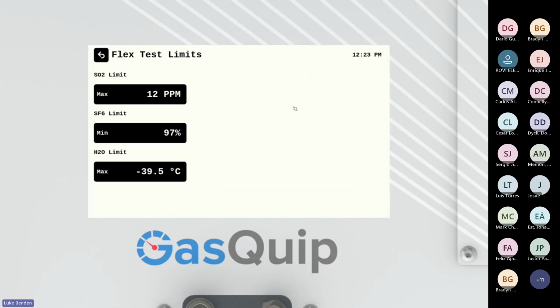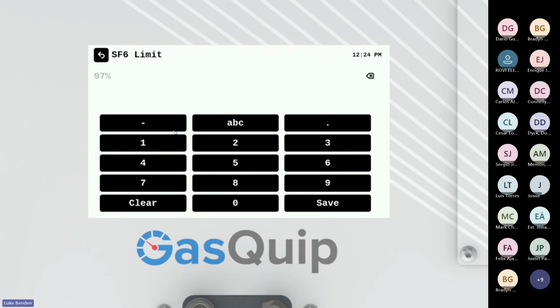This test limits area is what we talked about earlier with setting those thresholds for the test to either be pass or fail. The SO2 limit, SF6 limit, and H2O limit are all a little different. So SO2 is anything above 12 ppm for a maximum amount of SO2 you can have. SF6 is a minimum. So generally speaking, you want to have at least a minimum amount of purity of gas. And then H2O is a limit of how much moisture you can have in the system. And like we said earlier, the drier you get, the lower into the negatives you go with a H2O reading. So you can go in there and change that. Just click on it and input whatever value you want. But those are the default values.